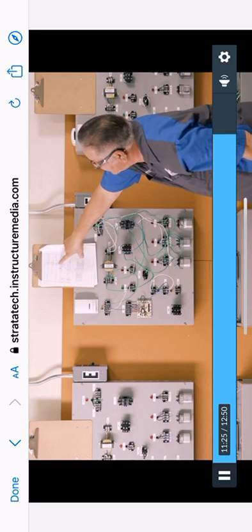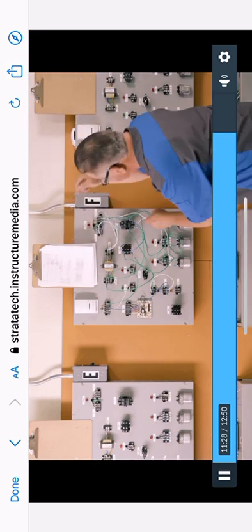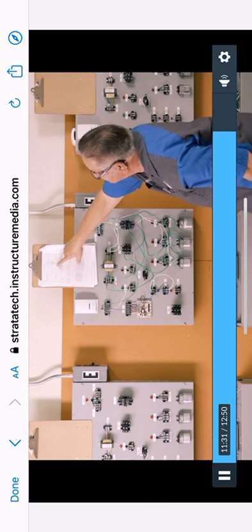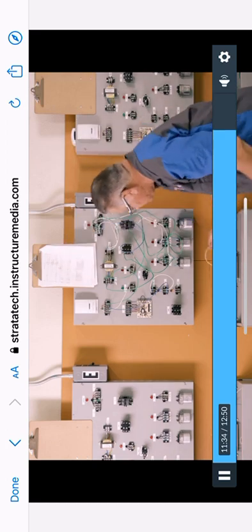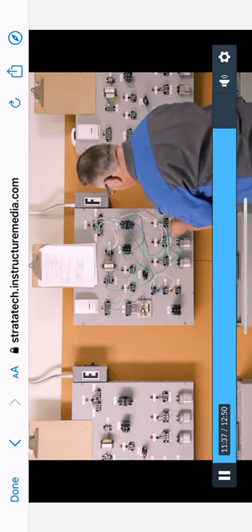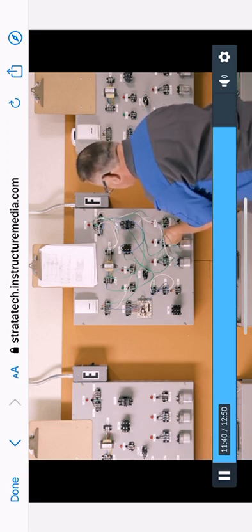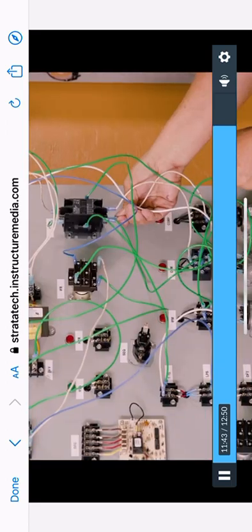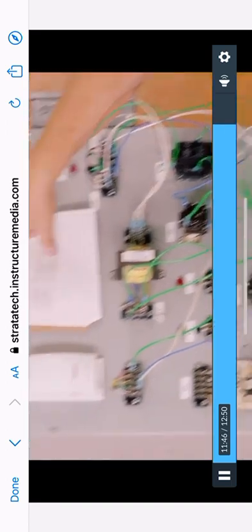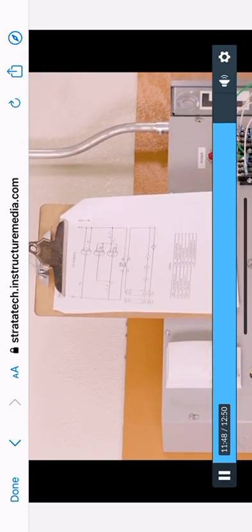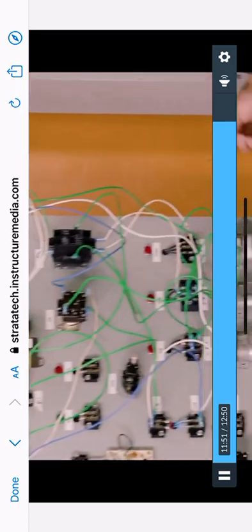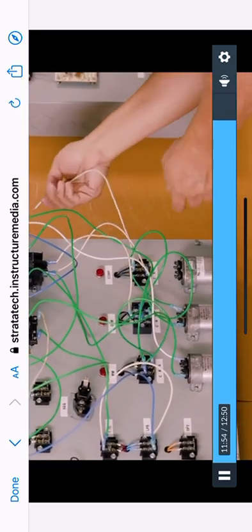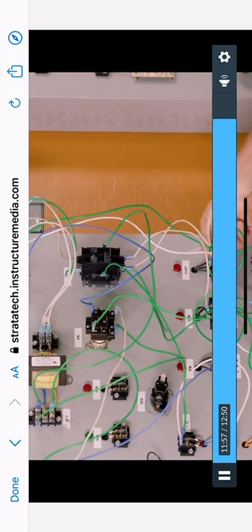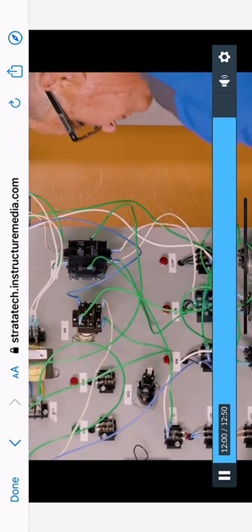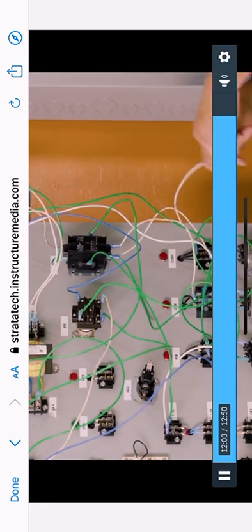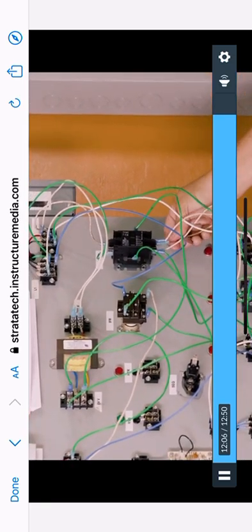Now what I got left is my compressor. I'm going to go from T1, which is the bottom of the contactor, to my C on my compressor. So I grab a wire, I go to my C terminal, and I go to the bottom of my contactor, right there, to T1. Now I'm going to do my run. I go from my run to T2. So I'm going for my run on the R, on the compressor, and I go straight up to my contactor, T2.